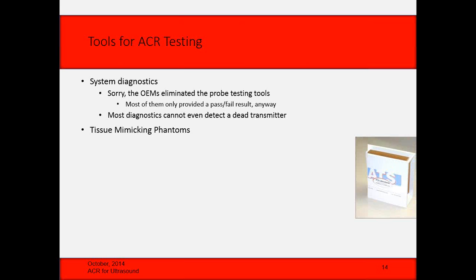So tissue mimicking phantoms, that's one of the main tools that we've used for years. There are some drawbacks though, because when phantoms first came out, we were able to fully test systems. We could actually test things and say, yeah, this is what the axial resolution is, and this was the lateral resolution. But the systems and the probes have become so much more complex that these days phantoms are unable to detect many system and probe problems that cause erroneous Doppler readings. And an erroneous Doppler reading can lead to an unnecessary angiogram or a misdiagnosis.